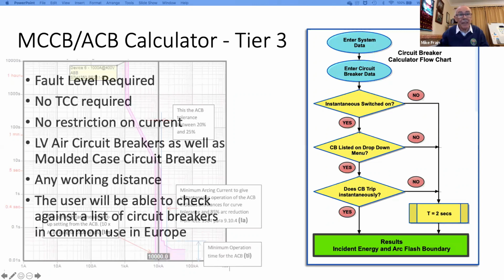The third one is tier 3. And in this particular case, all that we need is a fault level, and it's for circuit breakers. And it's the method that I've put together, which allows circuit breakers, as long as they appear on the system, and we're going through this very quickly, but what we're looking at is making sure that the disconnection time, where the instantaneous is switched on, is taken into account, and that produces an incident energy level and an arc flash boundary.